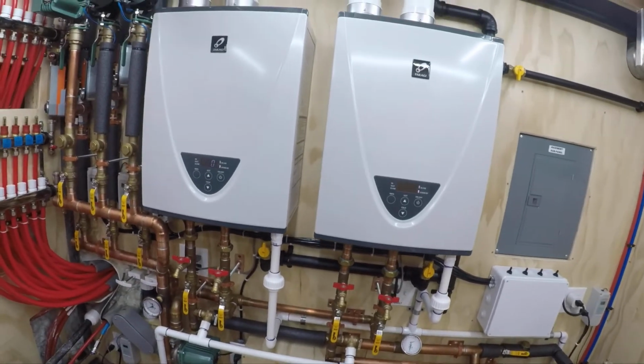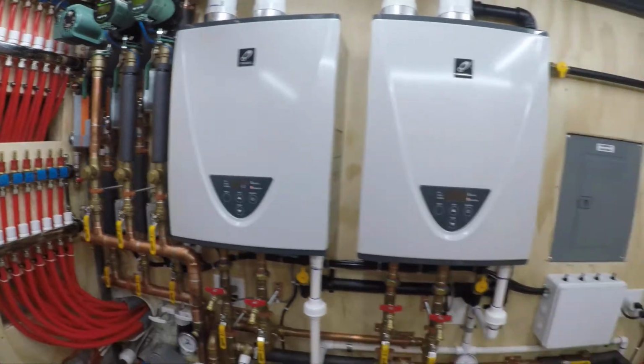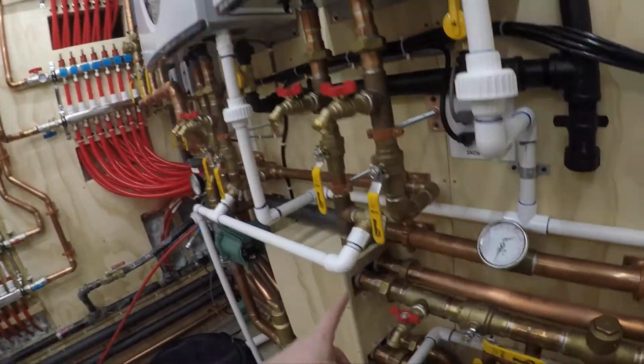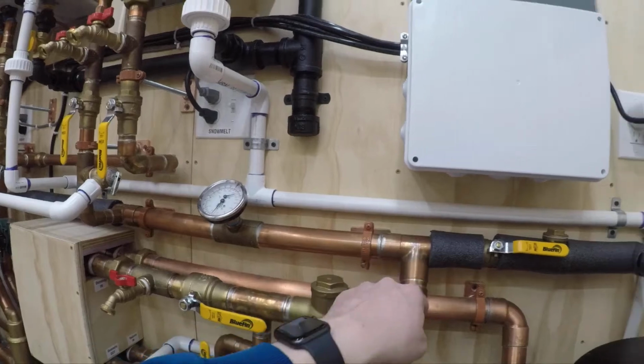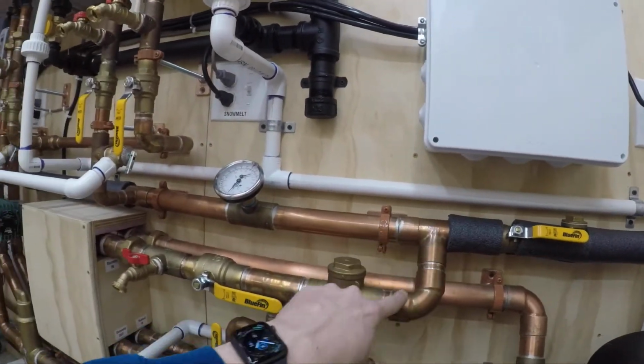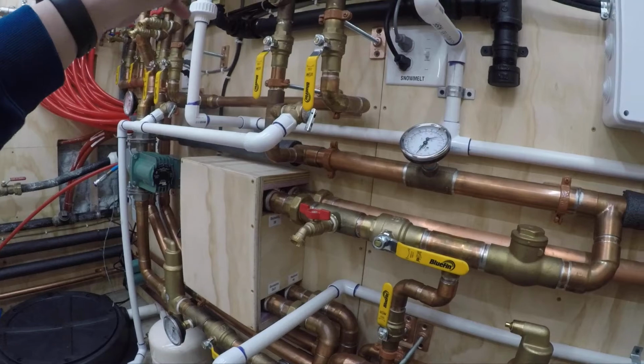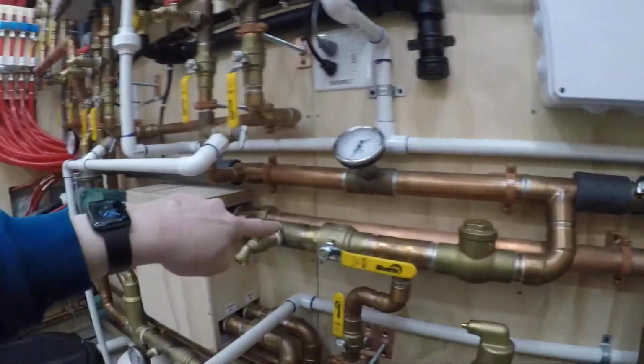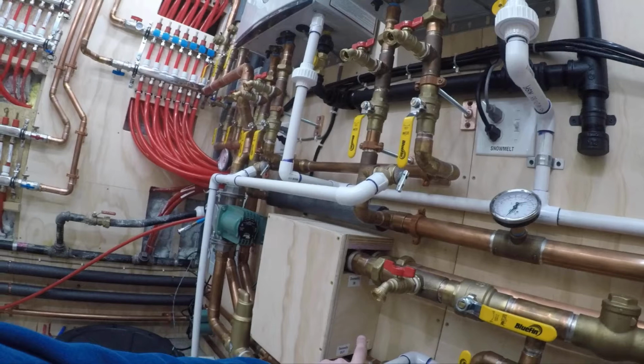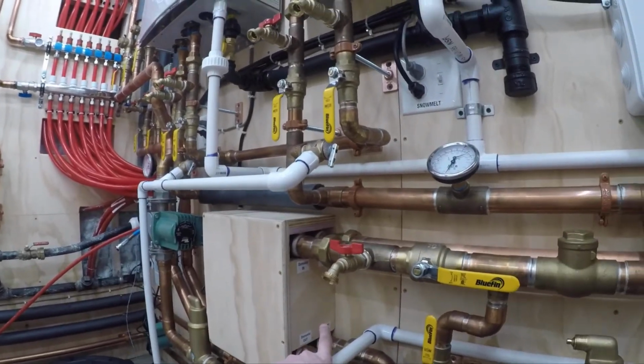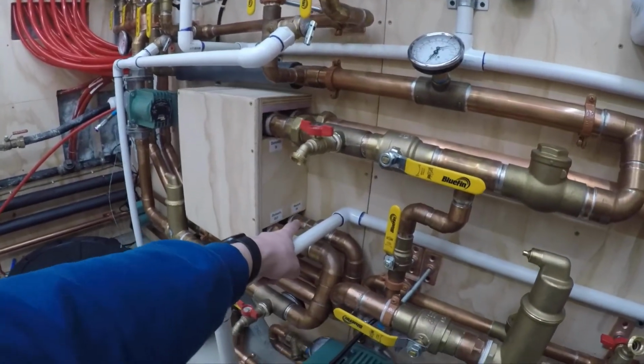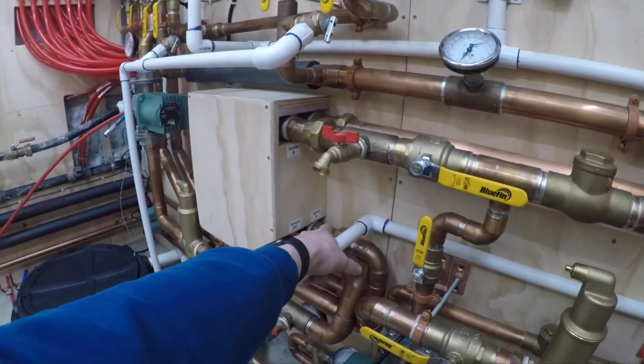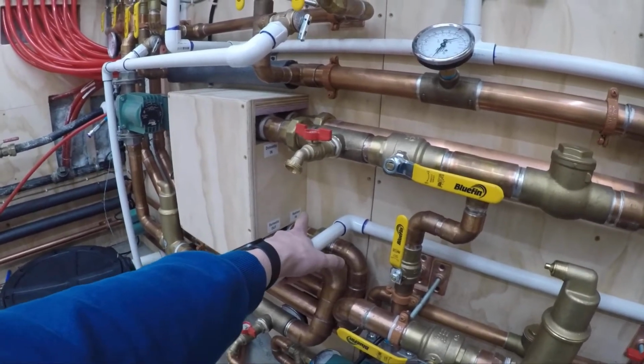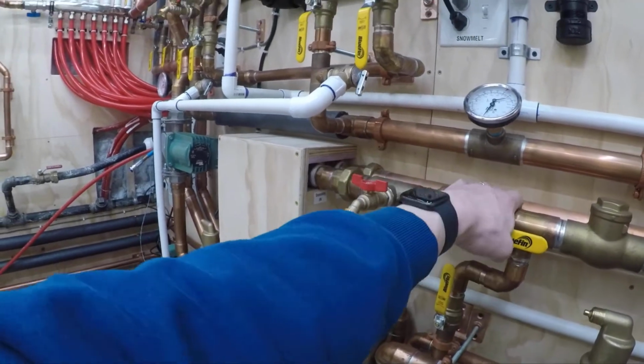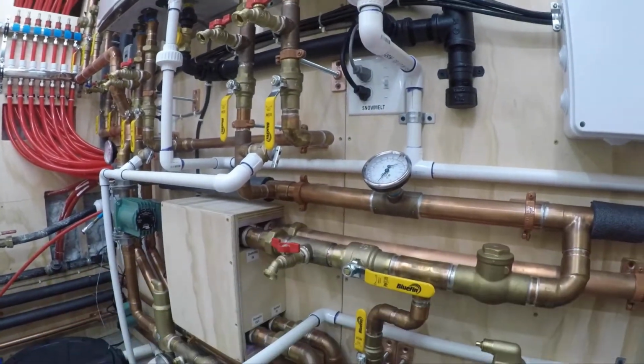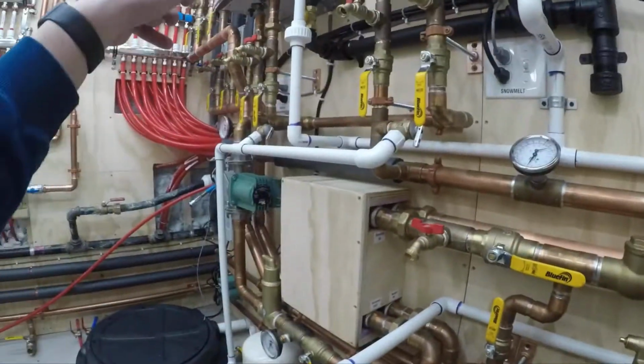okay, until the demand is satisfied. But what's going on the other side, as this hot 140 degree water comes down here, it's not really needed in the tank. It's just going in, out, back to the heaters. Coming out at 140, going in, going out, back to the heaters. But what's going on is on the opposite side of this flat plate, I have cold water, or glycol actually, cold glycol coming in on the bottom, picking up heat, stealing heat from this primary loop, and going out, okay, over here to my radiant stuff.